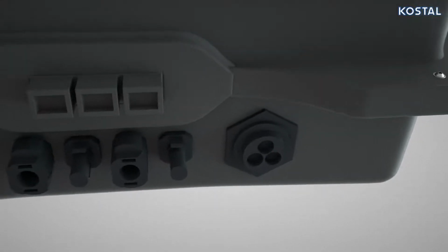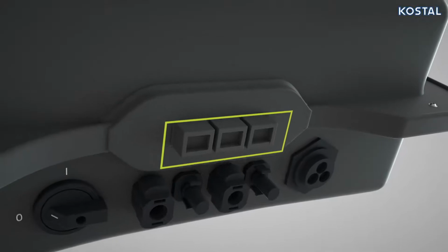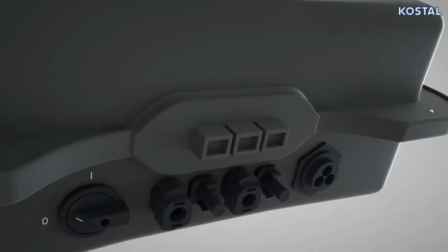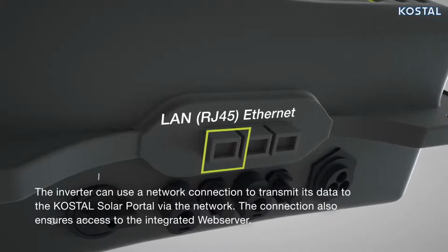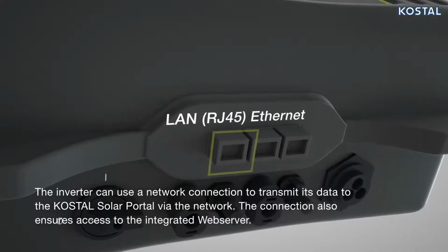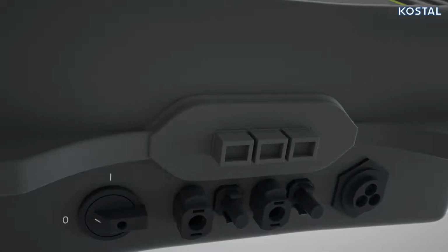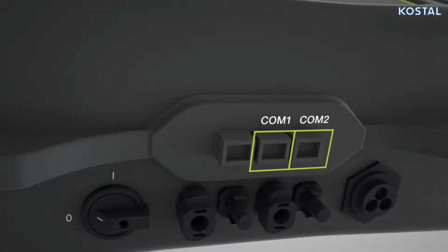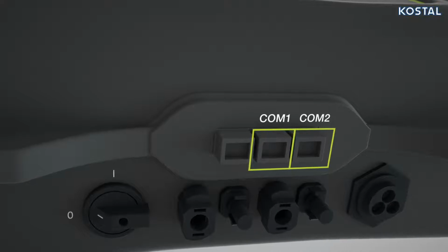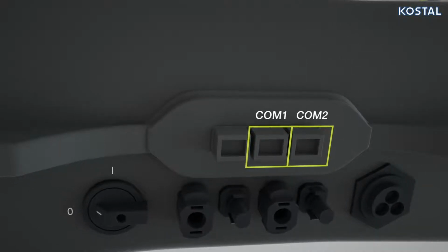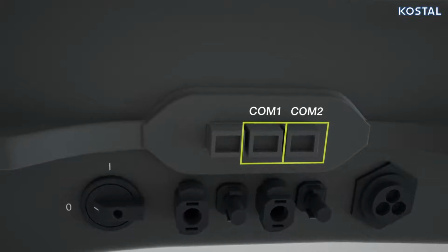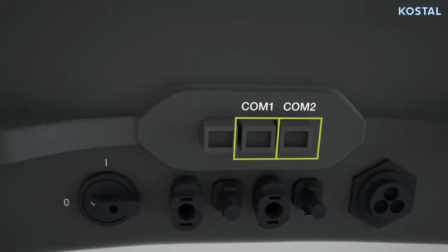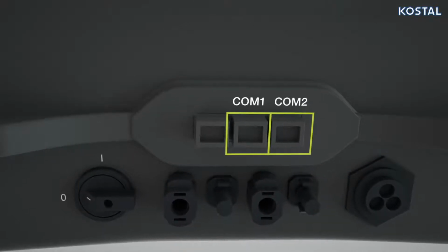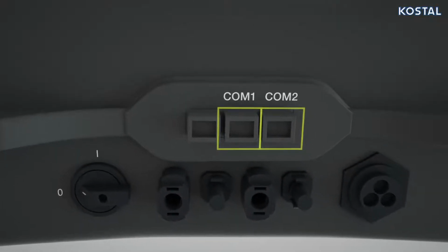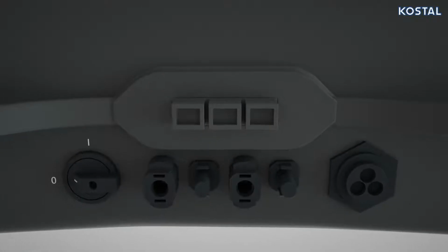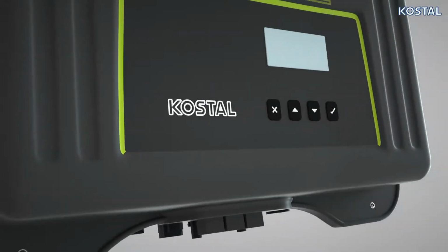The communication interfaces of the PIKO MP Plus can be seen above the DC connections. The Ethernet interface allows the inverter to be integrated into the local network. The COM connections are used for communication with external devices, such as the KOSTAL Smart Energy Meter. Connect this with COM1 if you are running a battery system on the PIKO MP Plus. If you do not have a battery, please use COM2 for the connection. The integrated display and control buttons are located on the front of the housing.